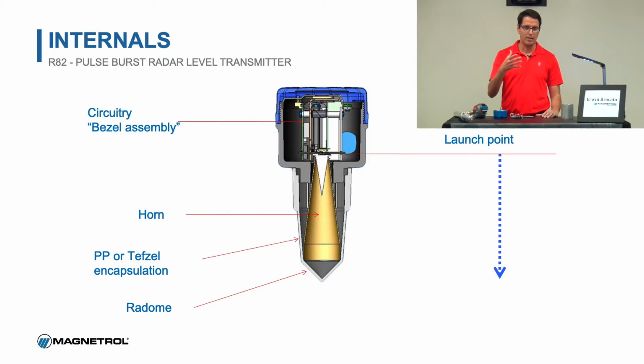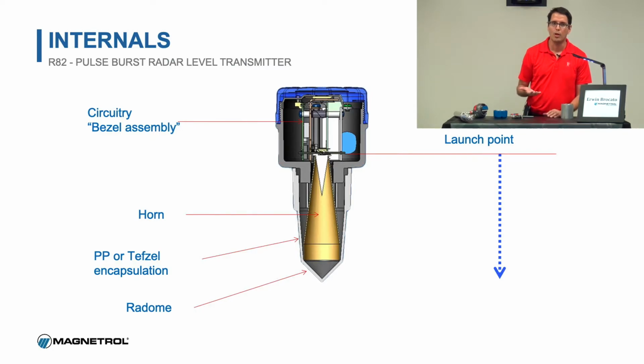And the cover itself is actually pretty advantageous because in a lot of these radar applications, you'll have any kind of condensation coming up and accumulating on that Teflon rod or antenna. And the good thing about the design of this particular device is that it will all just trickle out or just drop off. Whereas with an ultrasonic, it would accumulate on the sensor and then it attenuates the signal because it is a sound-based device and it won't work correctly.